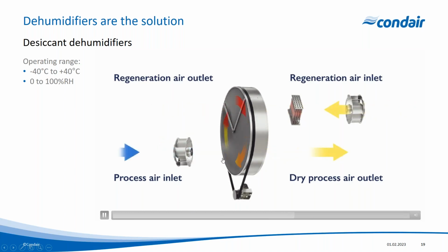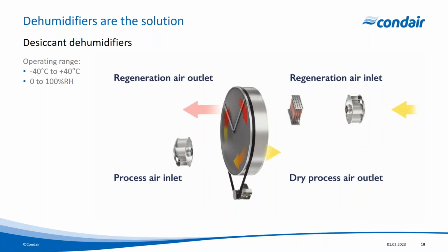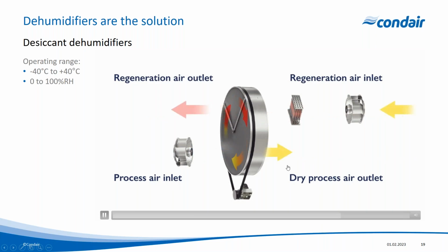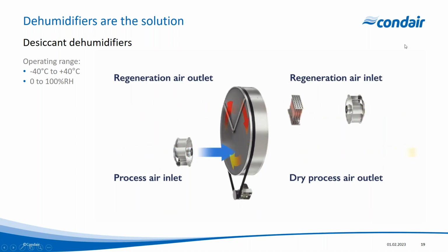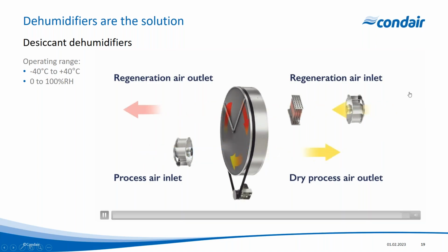Now you do get a slight heat gain as those moisture molecules release some of their heat as they're captured by that desiccant wheel. But it's not a huge deal. So we've got our dry air going back to the cold store. But that gives us a problem because we've now got a desiccant rotor that's holding on to all of this moisture.